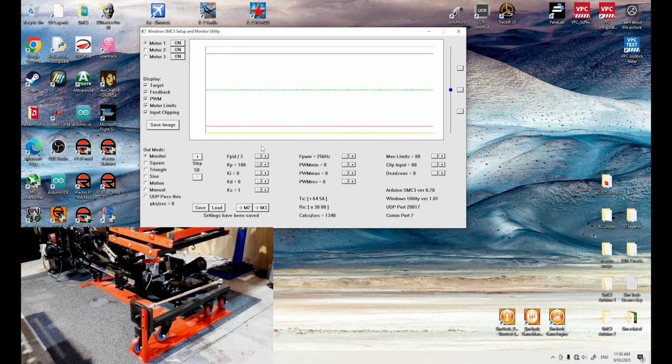So let's start. I normally start my proportional at 100. Now we're going to step back down to 10 on the step, so we're not increasing our parameters too much, because I wouldn't go to 50 on my minimum pulse width modulation. A maximum of 40 is where I would go there. Otherwise, I'm starting to introduce noise and it will have an adverse effect on my motors. They'll start to jitter and rock and move uncontrollably.